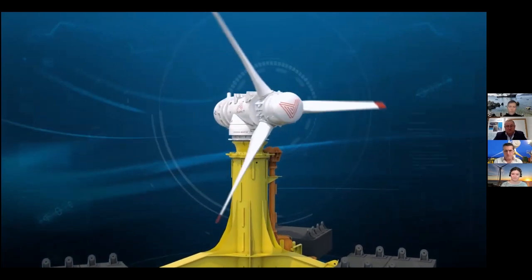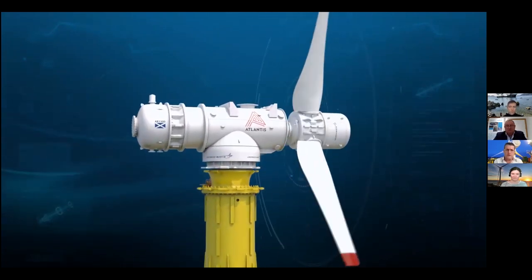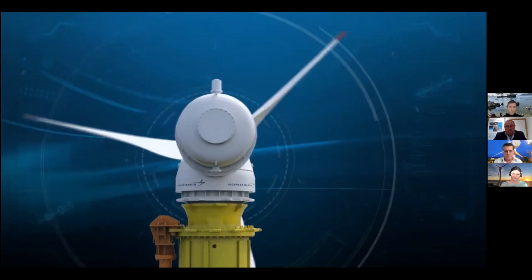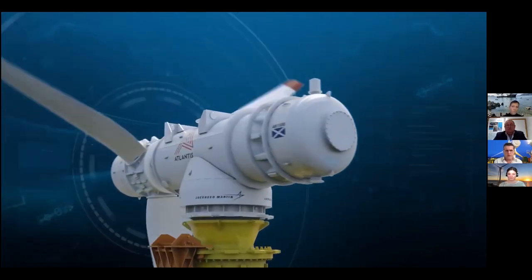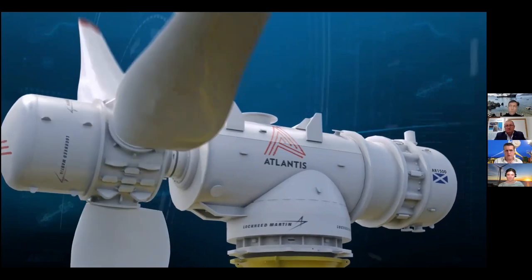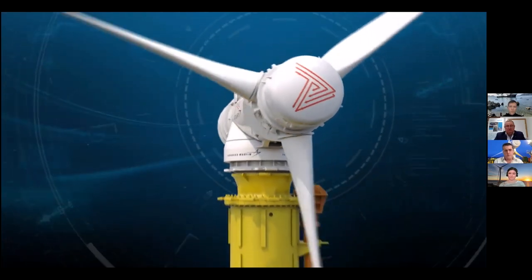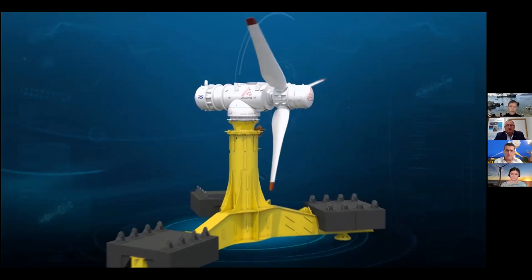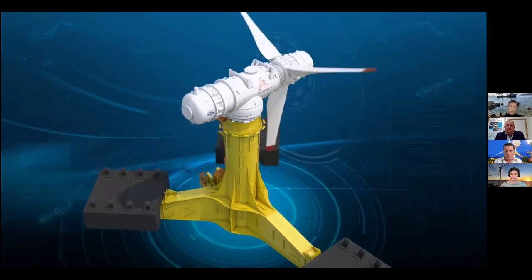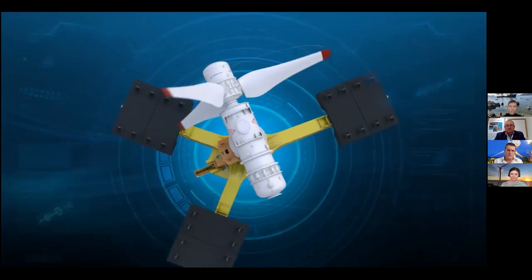The biggest change — which is no different to wind — is maximising rotor size and rating, which is critical to levelised cost of energy. The biggest step forward in reducing balance of plant costs is that we're now designing for up to eight turbines to collectively connect into a subsea hub. We've built a four-into-one version already and deployed it at MeyGen. That allows eight turbines to generate through one export cable, significantly reducing balance of plant — you've lost seven export cables and seven converters, running in a partial fixed frequency regime.